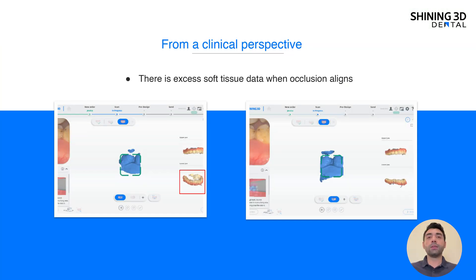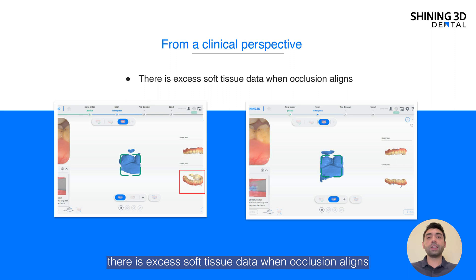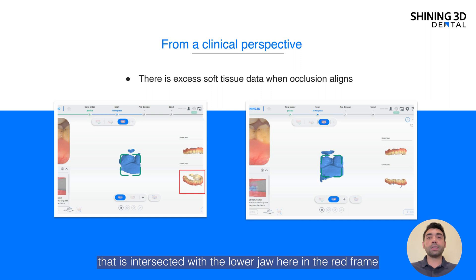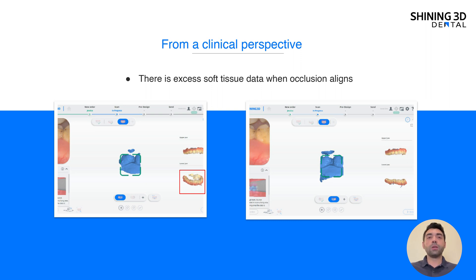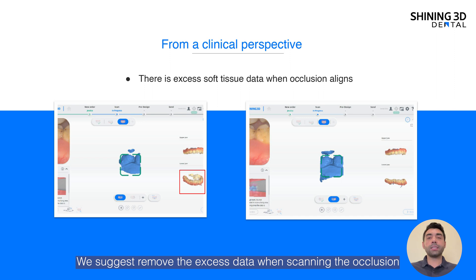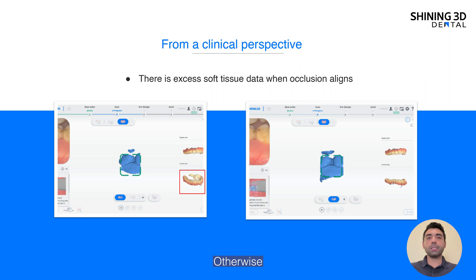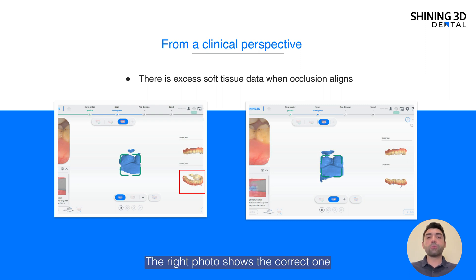Fourth, there is excess soft tissue data when occlusion aligns. The left side photo shows upper jaw information that is intersected with the lower jaw, shown in the red frame. We suggest removing the excess data when scanning the occlusion, making sure there is no interference during the process. Otherwise, it will affect the occlusion accuracy. The right photo shows the correct result, where the data is clear when scanning the occlusion.